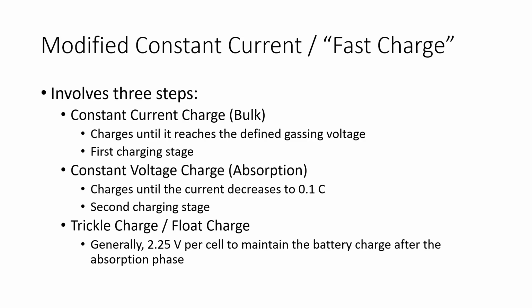After that, you're going to pivot to a constant voltage charge, or the absorption phase. And in this phase, you're going to let the battery take whatever amperage it wants. Just like in the initial example with jumping off a vehicle. Only in this case, we know that the state of charge of the battery is already 50-60%. So it's not going to take the 10 amps. So that's good.